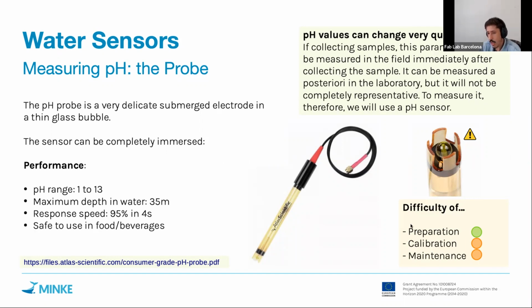Important to consider is that the sensor needs a very simple preparation: it needs to be calibrated, we'll see how often, and it needs to be maintained, especially for cleaning, because all these crevices will accumulate dirt and biofouling, so it will be necessary to maintain and clean it, as we will see later on.